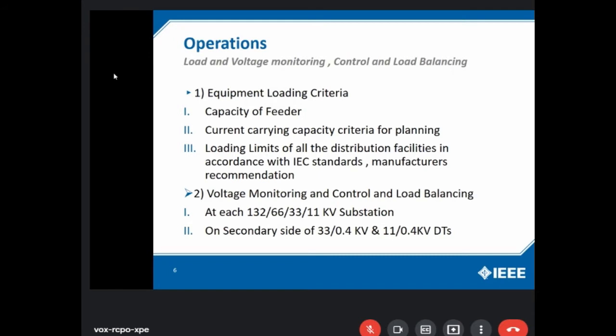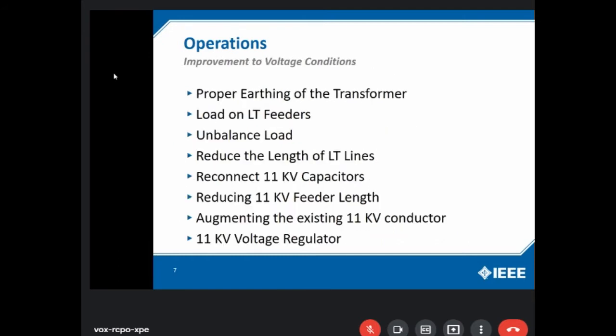The defined voltages are 132, 66, 33, and 11 kV for the substations on the primary side, and on the secondary side of the equipment it is 33 kV. For the 33 kV it's 0.4 kV, and from the 11 kV side, it's 0.4 kV for the distribution transformer. And there are then methods for improvement of the voltage conditions.